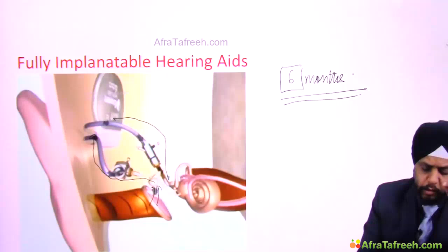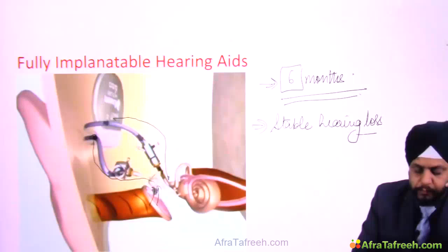Okay, number one. And number two, the patient should have a stable hearing loss. If his hearing loss is progressive, then you cannot use these implantable hearing aids. Why? Because if the hearing loss changes after 1 year or 2 years, you cannot change the hearing aid. All right, so he should have a stable hearing loss, and he should have used the external body worn hearing aid for 6 months regularly, and he should have a gain with those hearing aids. Okay, so these are two prerequisites for using an implantable hearing aid.